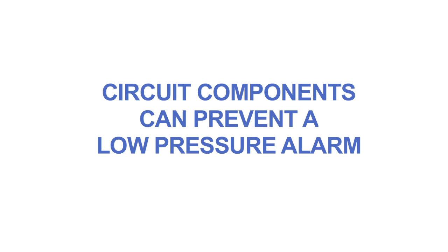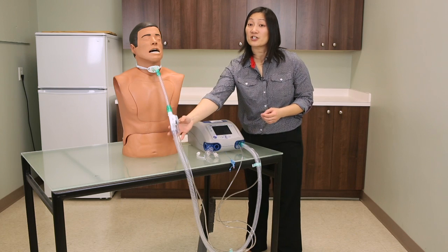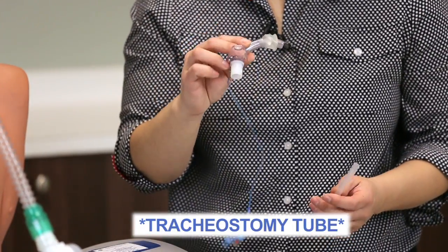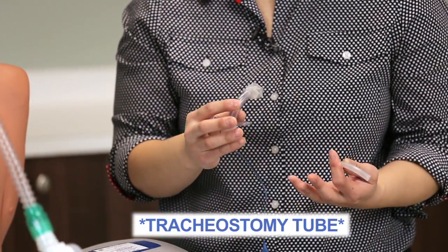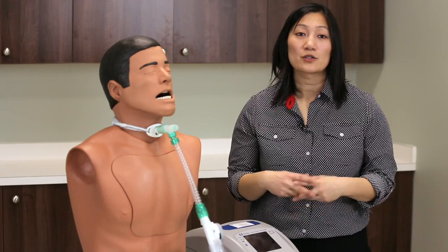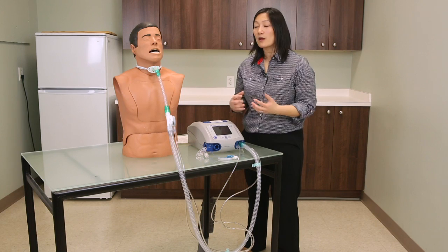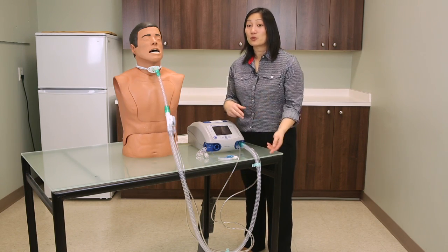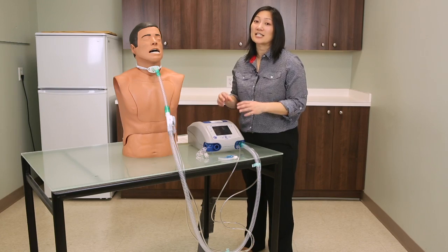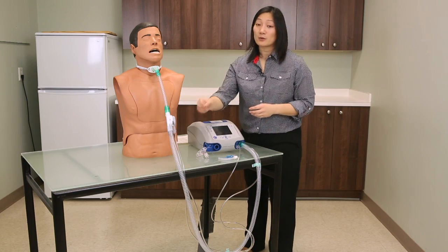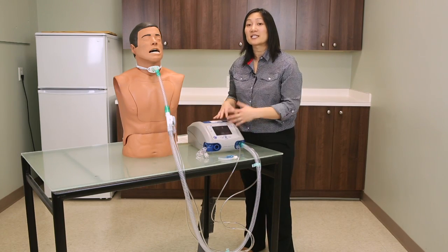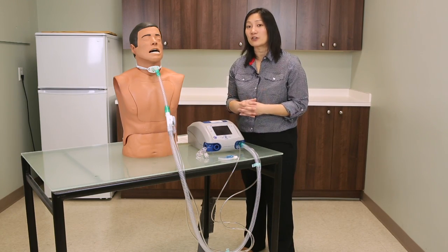The challenge with the low pressure alarm is that circuit components such as the ventilator tubing, the inner cannula, and tracheostomy can prevent the low pressure alarm from actually ringing or visibly alarming. This is due to the back pressure generated within the circuit when the ventilator is attempting to give a breath — that pressure is measured distally and is mistaken as pressure that can be delivered into the lungs.